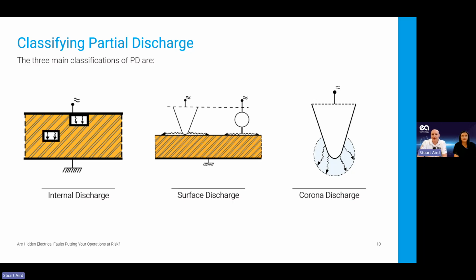The next type of discharge that we have is surface partial discharge. So we've got tracking across the outer surface of the insulation. You see this quite often in cable terminations, if the cables are too close together, or where the cables are a bit too close to the earth metalwork within a compartment. Also bushings and busbars where they go through from panel to panel, you start getting this surface tracking. You'll see something on the outside of that insulation. And again, if we think back to those emissions, we will get light, so you would see little arcs going across the surface. You would be able to hear it, and you'll be able to smell it and things like that.